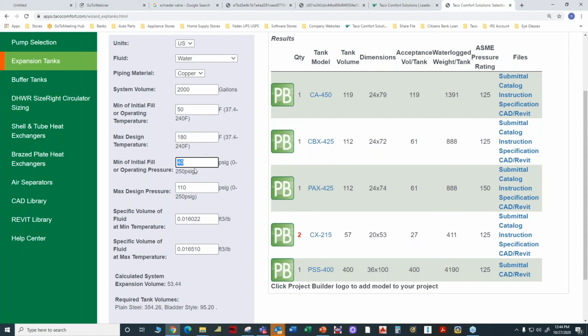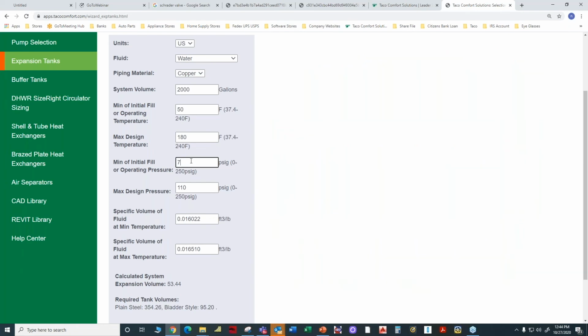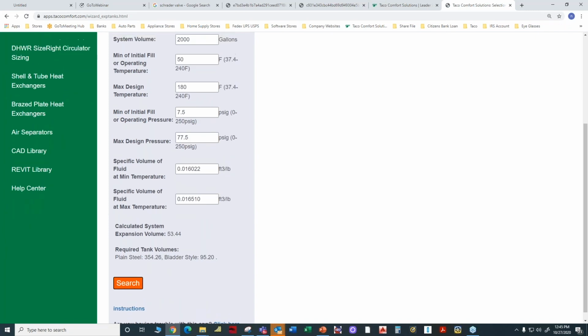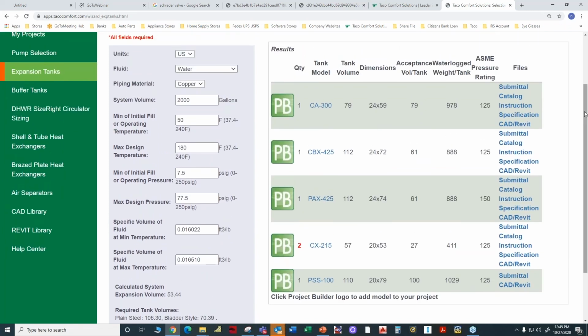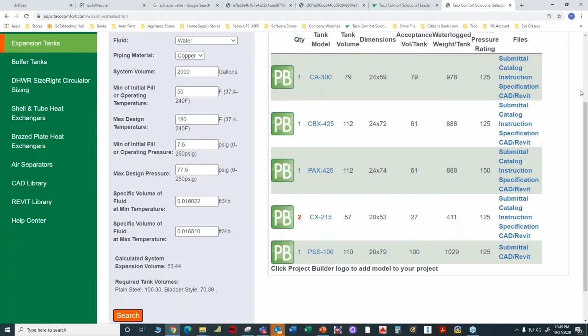I'm going to change that fill pressure to 7.5 because we said that's what we want for minimum at the top of the building. And the maximum pressure at the top of the building would be 110 minus 32.5, which is equal to 77.5. Then I go down here and click on search. If you'll notice, the expansion is still exactly the same, because remember, the expansion is a function of the volume and the temperature difference. So the expansion is exactly the same, but look what happens to the tank. The tank gets physically smaller because of the pressures.